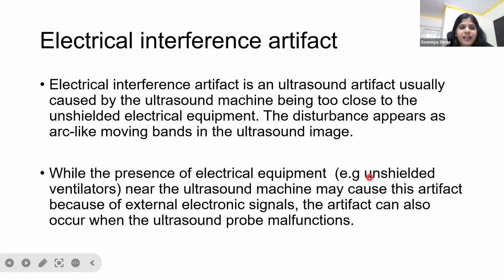Coming to the last artifact, electrical interference artifact. Electrical interference artifact is an ultrasound artifact usually caused by the ultrasound machine being too close to unshielded electrical equipment. The disturbance appears as arc-like moving bands in the ultrasound image. While the presence of electrical equipment like unshielded ventilators near the ultrasound machine may cause this artifact because of external electronic signals, it can also occur because of ultrasound probe malfunction.